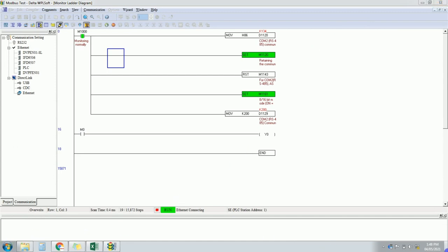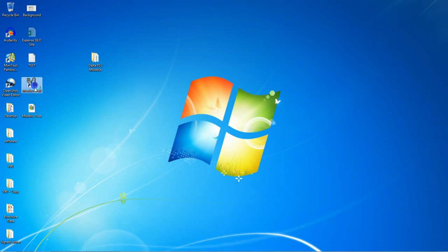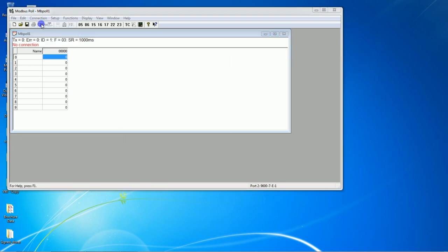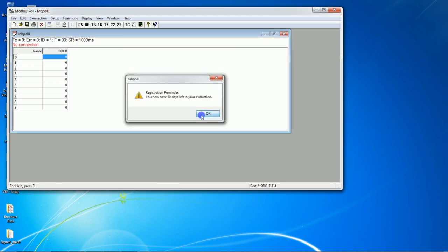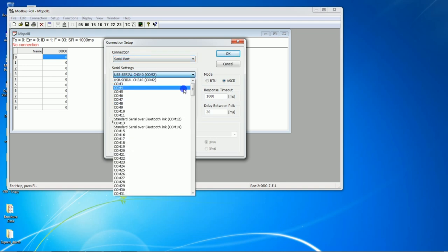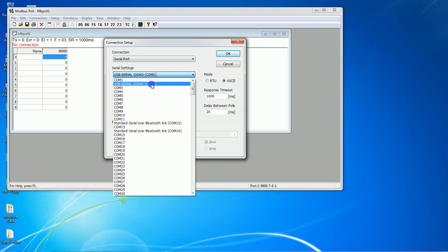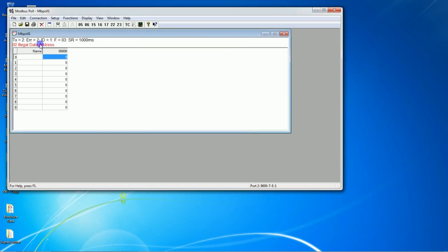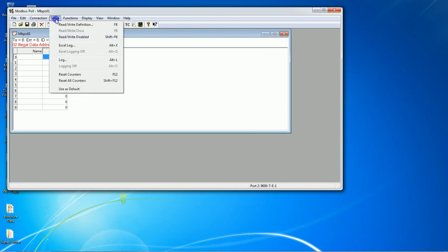Now just open the software we installed previously — Modbus Poll. You can also use Mod Scan or any other simulator; I prefer Modbus Poll which we recently downloaded. Go to Connection and click Connect. We are connected through serial port, so serial port is selected. Select COM2. We have 9600 baud rate, 7 data bits, even parity, one stop bit — this is ASCII mode — and response time 1000 ms.